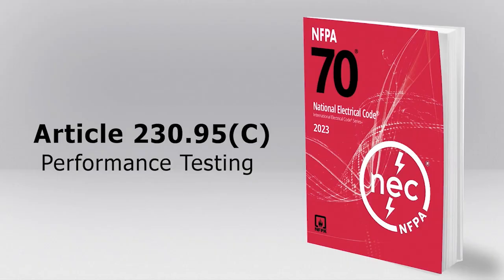We want to energize the building, but who says we have to performance test? Well, these guys right here do. The National Electric Code has an article, 230.95(C), that is performance testing of ground fault systems. And here's the deal. If you're an electrical inspector and you're not asking for the test record on initial energization of a building that says the ground fault system has been tested, then you could have real liability there.